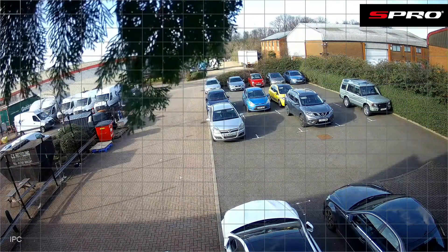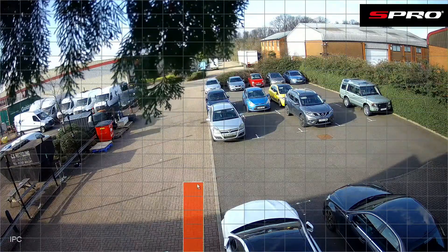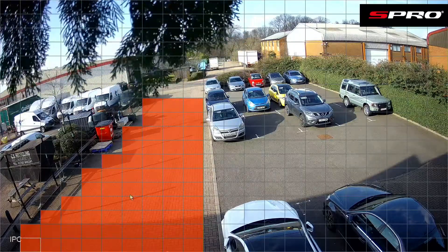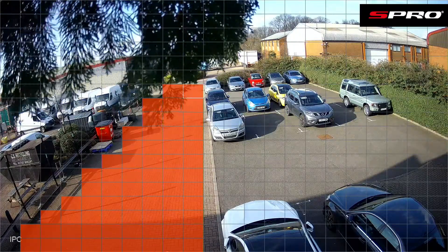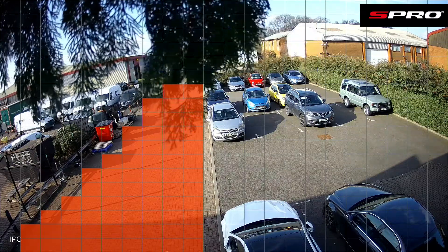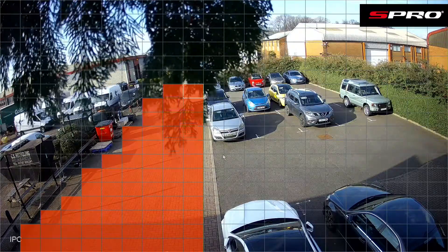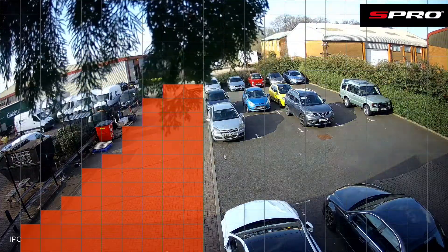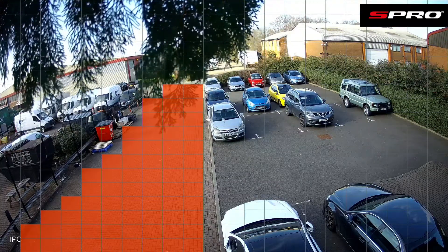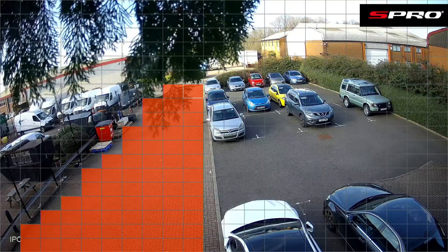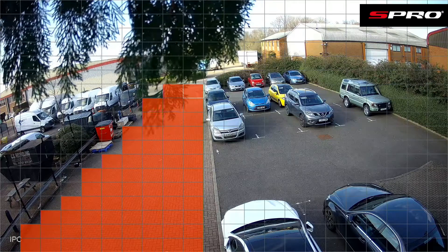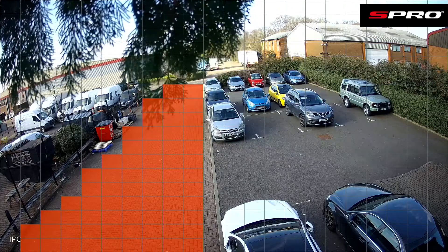With standard motion detection you can set up regions with different thresholds for what percentage of the region needs to be occupied in order for an alarm to trigger. This can be one way of customizing motion detection to the environment, but we're still working in the realm of standard motion detection, and in this situation it isn't likely to do much about the overhanging branches, which as the wind moves them will take up more or less of the region at different times.